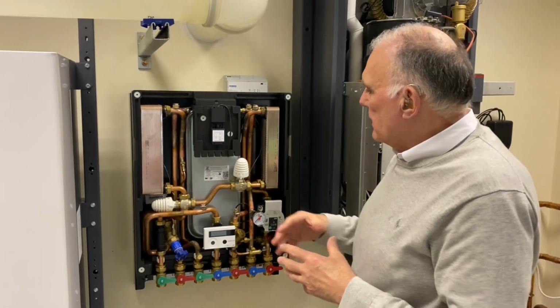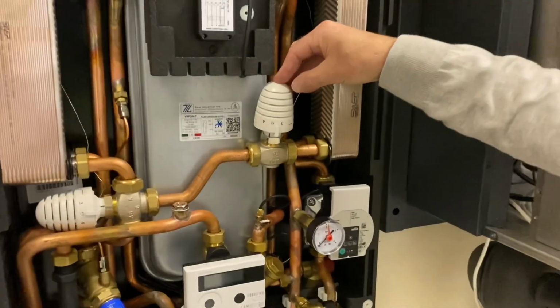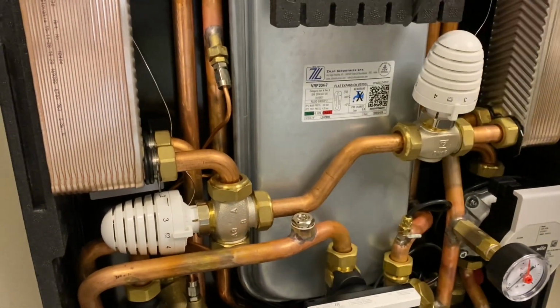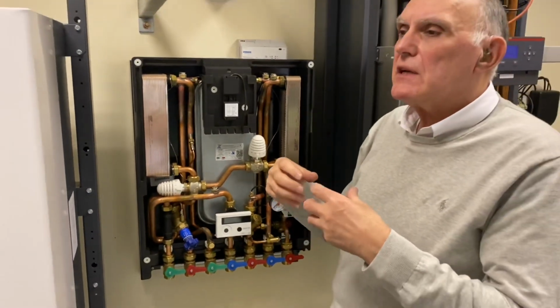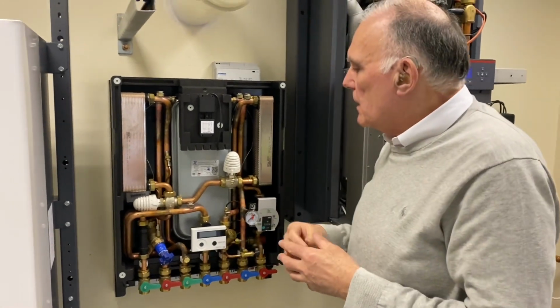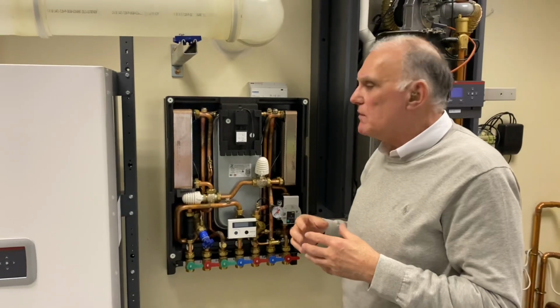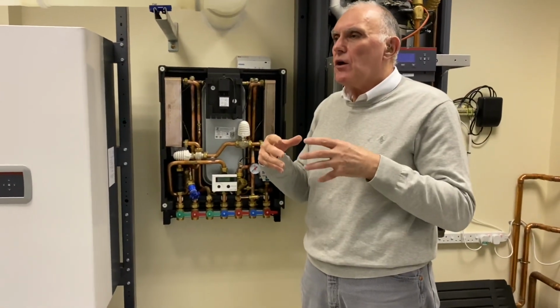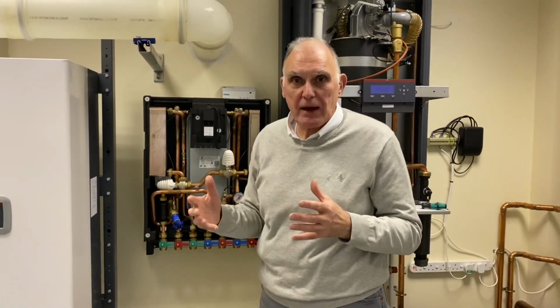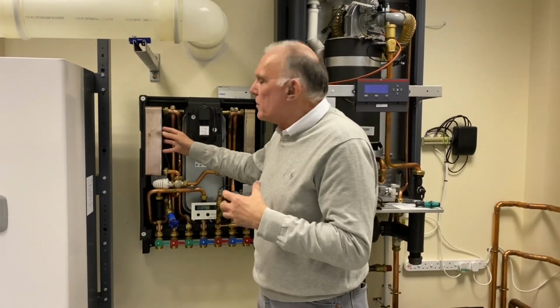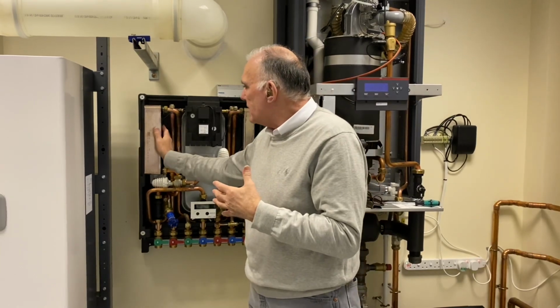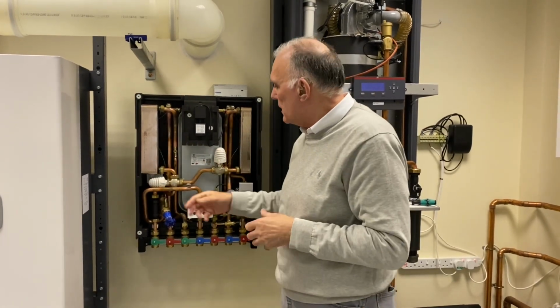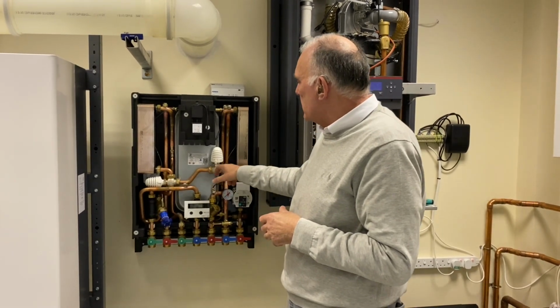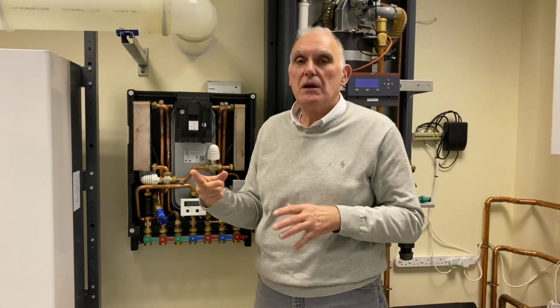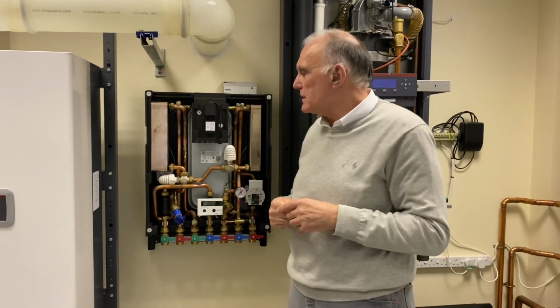The thing I'd like to point out now is we've got a proportional valve here and a temperature control for the flow to the space heating. Because the primary flow returns are obviously controlled by the main plant room and will be at high temperature, one way it scores points over a combination boiler is this: if the domestic hot water demand isn't particularly high, maybe a shower, maybe just a basin running, all of the water that's available for heating the plate heat exchanger would not be used, because the energy in that is more than enough to satisfy the domestic hot water usage. So the proportional valve here will allow some circulation through the space heating, so there's actually possibly simultaneous heating of domestic hot water and space heating.